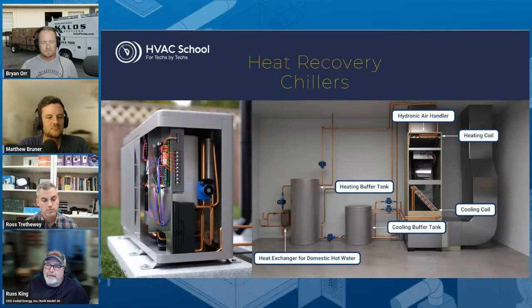Yeah, just using the outdoor temperature. And then you can take into consideration economic balance points too. So you can get really, really complicated with that topic. But yeah, I would say probably the outdoor temperature sensor is probably one of the best ways to go. Big difference if you're talking about natural gas or propane, that's a very different thing. And so when you're talking about a dual fuel strategy, that's when getting really detailed on the economic side makes a lot of sense. Yep.